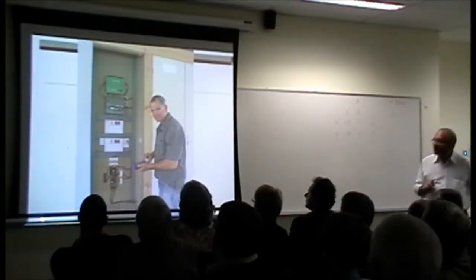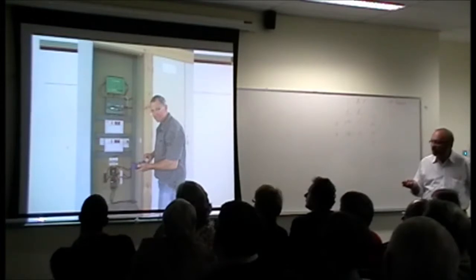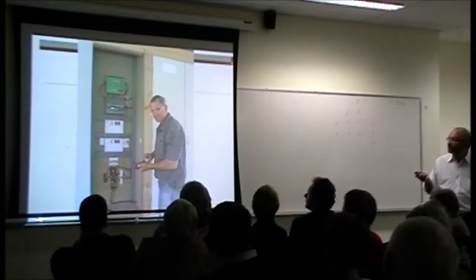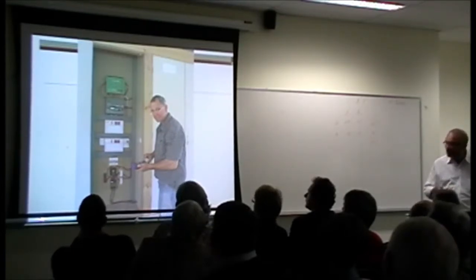That's the electrician putting it in. So there we have the electronics, the SMA grid interactive inverter, the 2 load centers, so one for essential and one for non-essential loads, DC charge controller, and the batteries are just behind the electrician there. All not a problem. The inspector approved it. The only thing he did want was some venting in the battery cupboard, so that's what those vents are for. But he was a happy camper. To my amazement, I was expecting a bit of drama there, but not a problem.